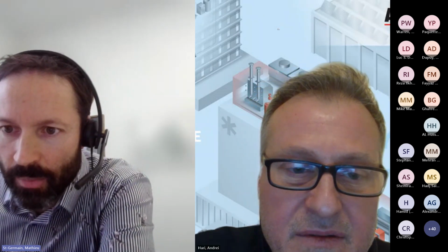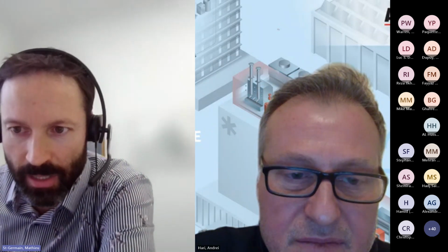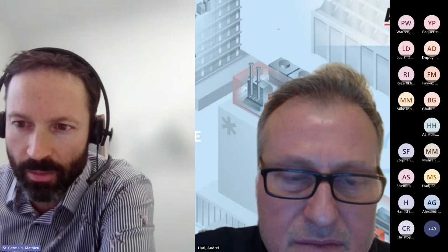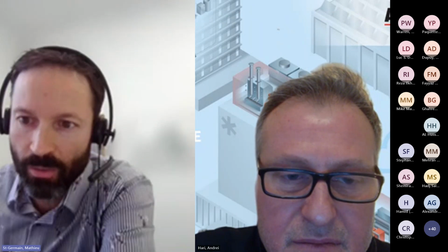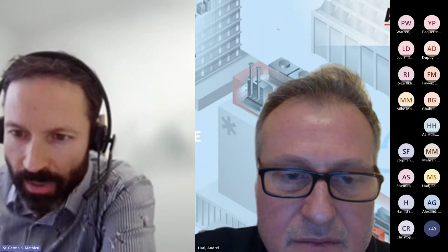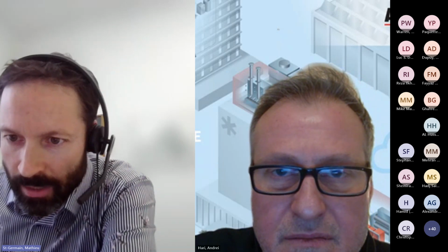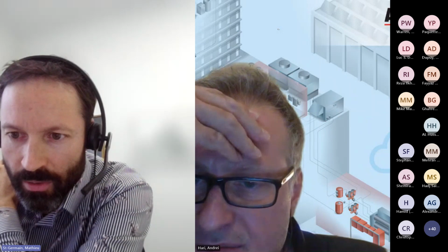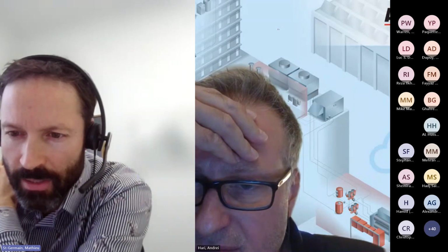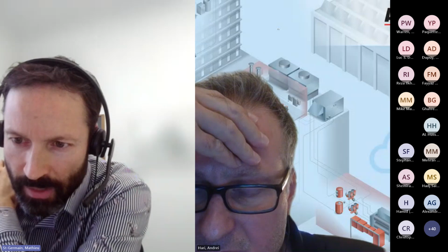Okay, thank you, Andrei. There's a written question from Derek. You want me to read it for you? Oh, sure. For a parallel pump setup, why have I seen the IPS display showing both running at the same speed, but one pump at very low or almost zero GPM and the other at design point? The piping looks identical leading to the parallel pumps. Should the IPS pumps be able to adjust themselves correctly? Is the controller different for a parallel pump VFD setup than for a duty standby rotation setup?